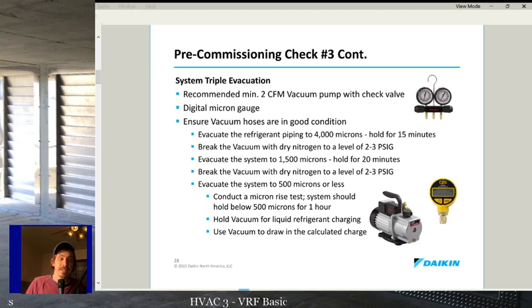The last one I did, which was only a 4-unit system, actually went beautifully. I took out a couple cores, got that thing down to 220 in a few hours and it held for an hour easy. But anyway, sometimes they're harder, sometimes they're easier. It depends on how long it's been open and so on and so forth. But it doesn't take much to make a vacuum leak. So holding for 24 hours is ridiculous.